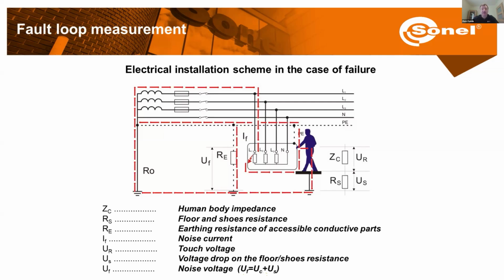But what happens in case we have a fault situation? Well, then some potential can appear on the cover of our charger. And here the cover should be connected through the protective wire PE, either back to the transformer or to the earth. So we are going to have some leakage currents flowing through the PE wire or flowing through earth, or in a situation where somebody will be touching the cover of the charger, then the leakage currents can flow through their body, and this person can get shocked.